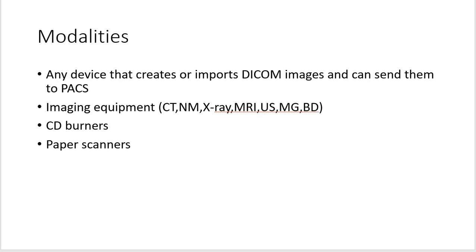A modality is any device that creates or imports DICOM images and can send them to PACS. The most obvious modalities are the imaging equipment: CT machines, nuclear medicine gamma cameras, x-ray machines, MRI machines, ultrasound carts, mammography machines, and bone density scanners. But CD burners in the hospital can also be modalities — if a patient brings in a CD that needs to be imported, you put the CD in the burner and it imports the images into PACS.